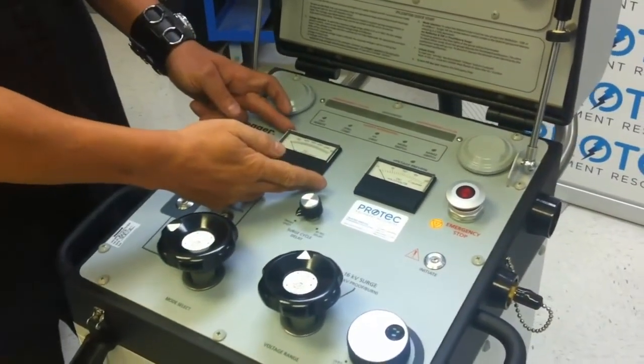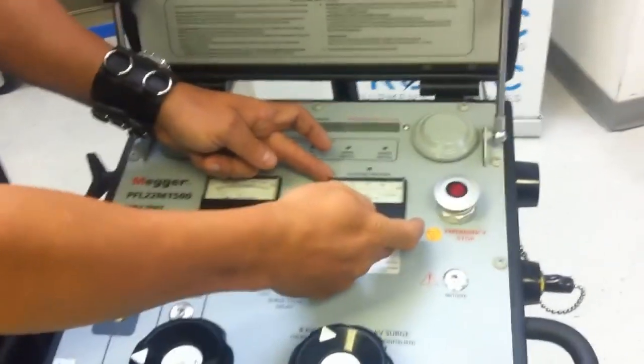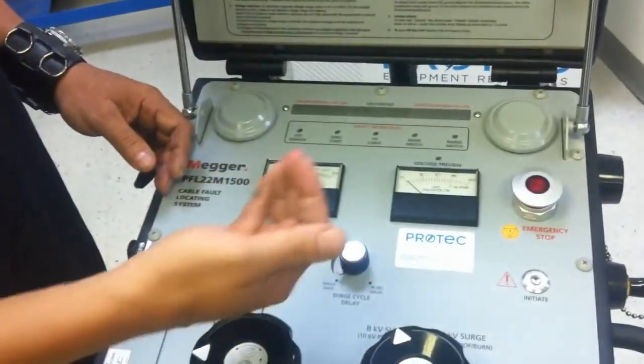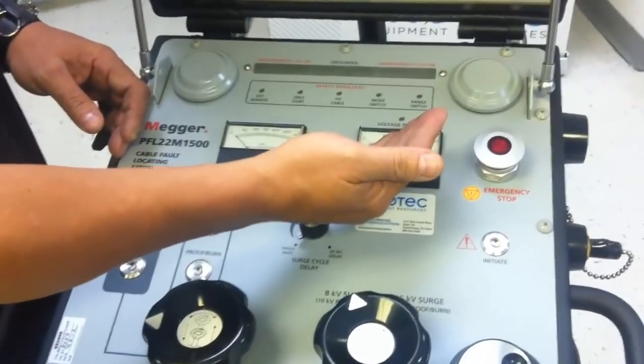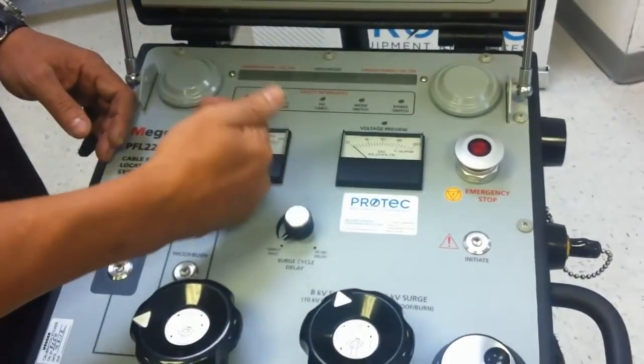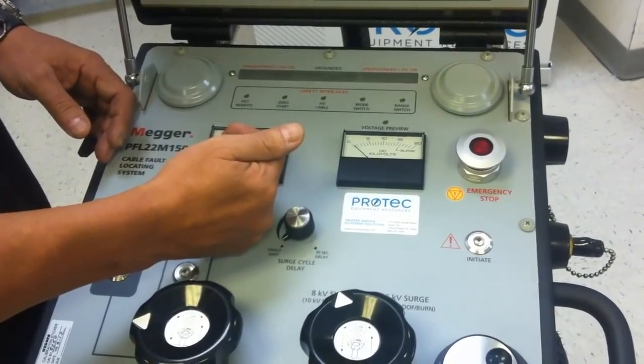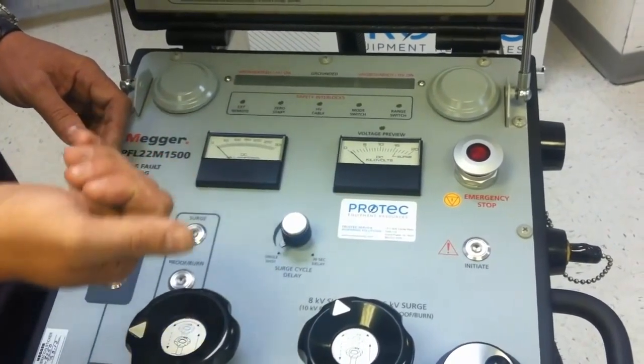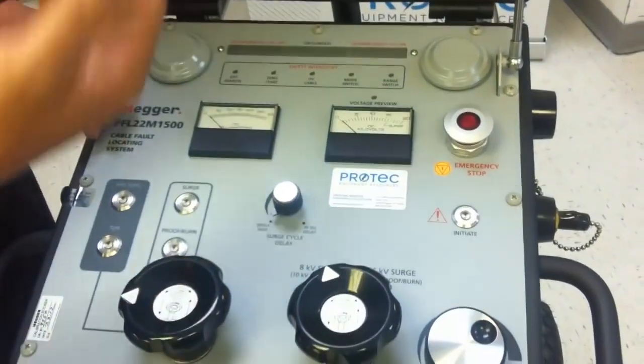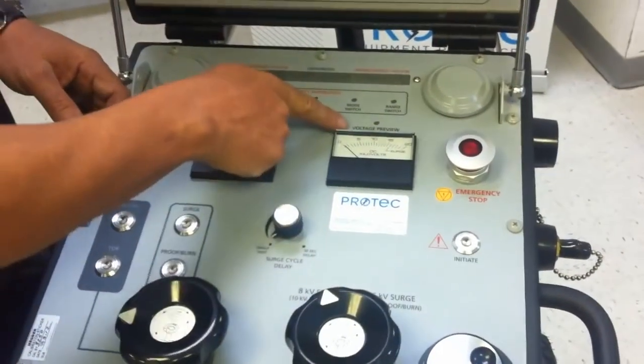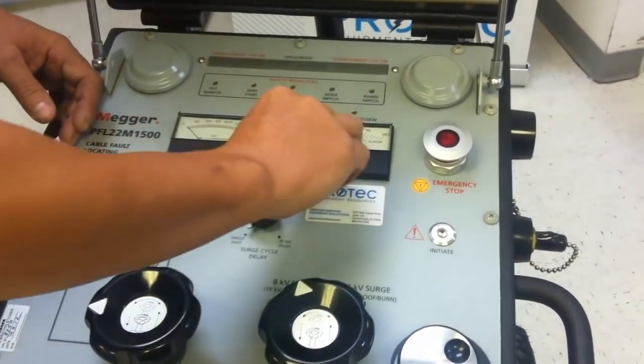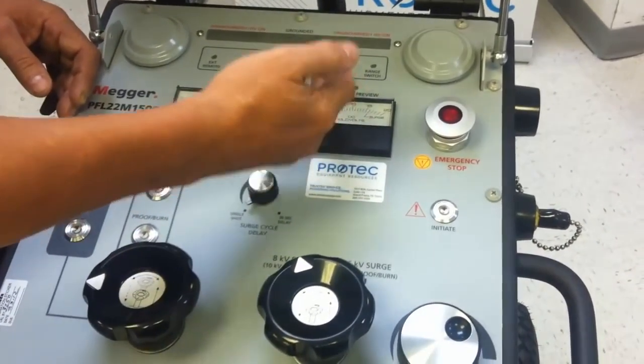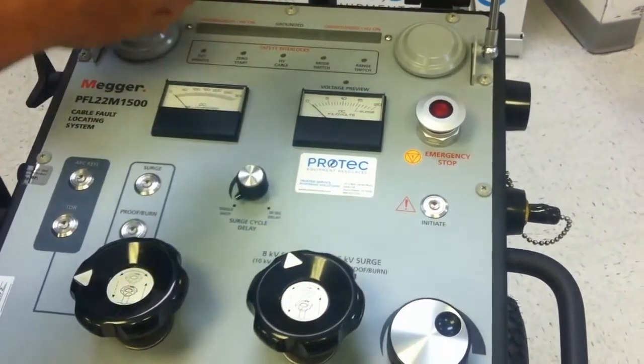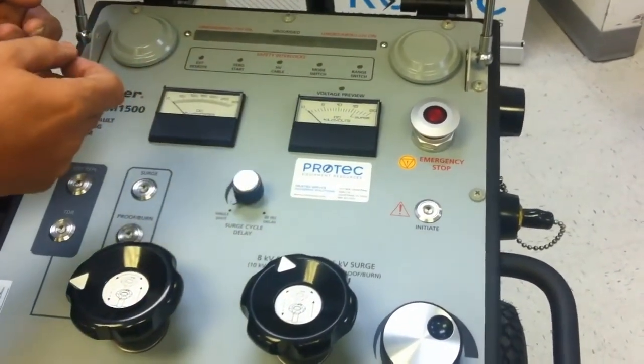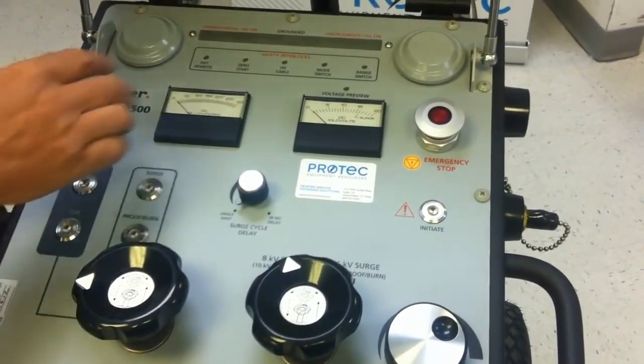We have the DC ammeter, the DC kilovolt meter. So again, if we're running a proof test, we can monitor the voltage that the circuit is holding. We can measure or document the amount of leakage current or fault current flowing. Also, when we're setting up our capacitive discharge, we have a voltage preview mode where we could actually bring the internal charging circuit up to the desired level, initiate, then charge the capacitor to that preset previewed value and discharge.